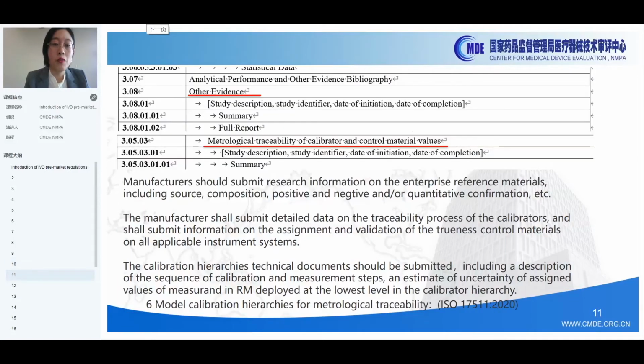Firstly, manufacturers should submit research information on the enterprise reference materials, including source, composition, positive and negative or quantitative confirmation, etc. Then the manufacturer shall submit detailed data on the traceability process of the calibrators and shall submit information on the assignment and validation of the trueness control materials on all applicable instrument systems.